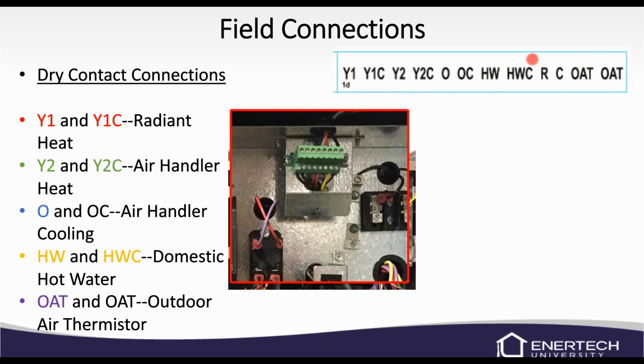So a real quick diagnostic tool, if the unit's not running and you think it should, disconnect this terminal strip. You don't have to unwire it, just pull it off, and jumper your Y1 and Y1C and let us know what it does. Does it run? If it does, then we know it's a control problem, not a unit problem. So it's a real quick way to know, do I need to look at the external controls, or do I need to look at the indoor unit?